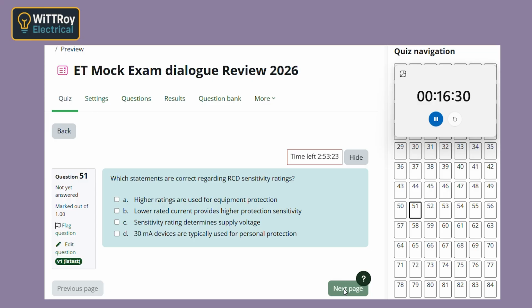Good question. In this question, sensitivity rating means the rated residual operating current. That is the level at which the RCD is designed to trip. It is not the exact trip value, but the rated level. So if it says 30 milliamp, it doesn't mean it always trips exactly at 30. Correct. A 30 milliamp RCD can trip a bit lower, like mid-20s milliamp, and that is still normal. The number is a rating, not an exact trip point.